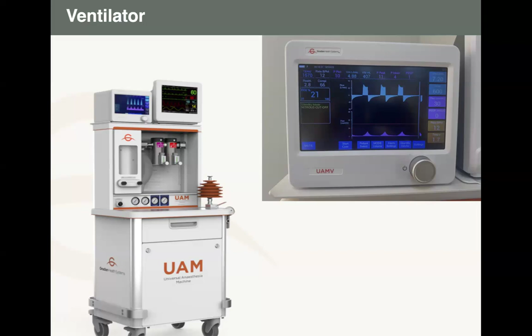Once you switch this machine on, this screen will show up, the one showing the machine, and after this the next one will allow you to select a patient, which means you either use the user ones or you go with the weights which are already saved in. So if it's 50 kg, 70 kg, 100, whatever. Once you select that, the machine will give you estimated ventilatory parameters for that patient. Once that is confirmed, and you think those parameters are appropriate for your patient, this is the time whereby you want to use the vent.